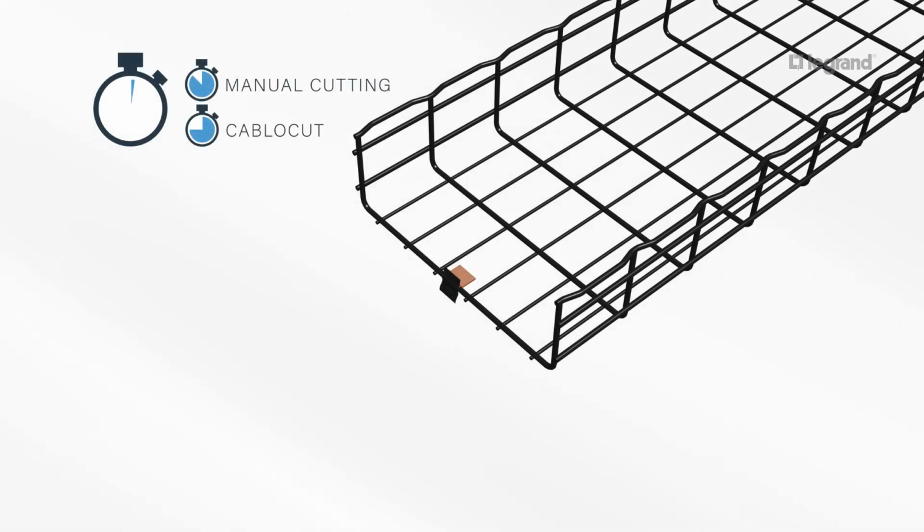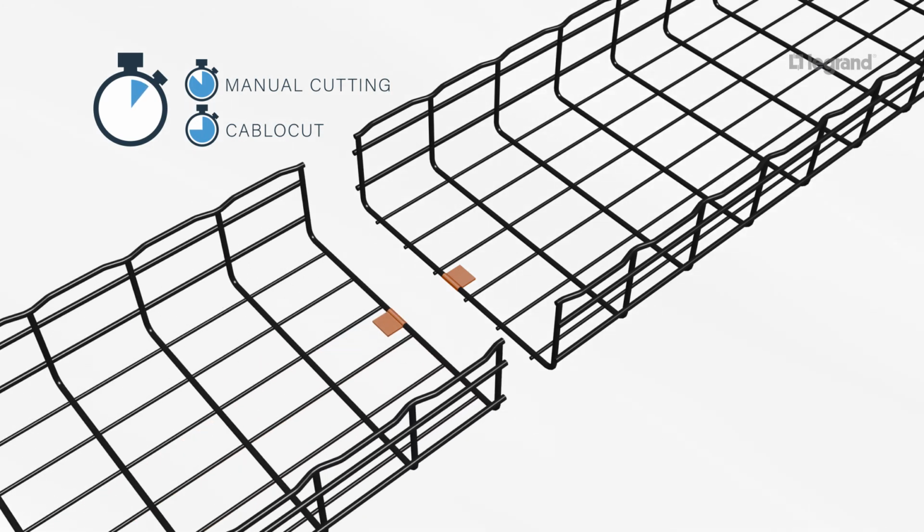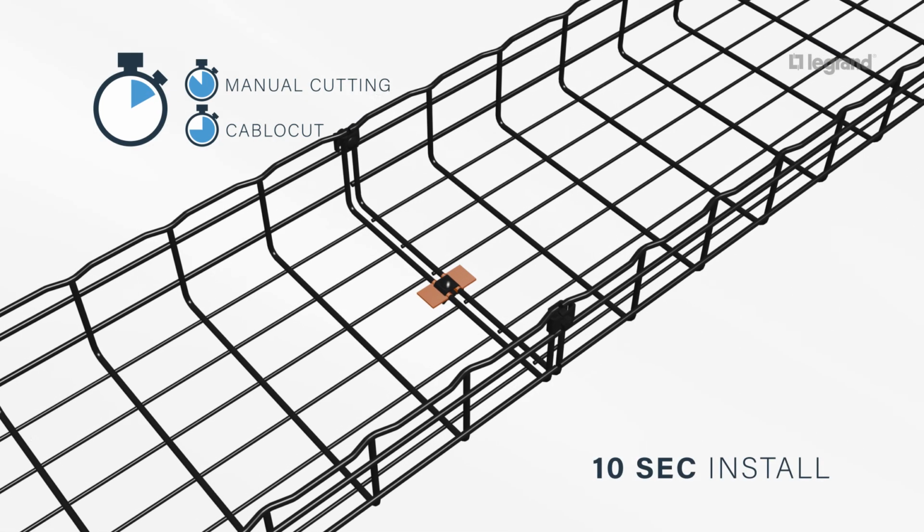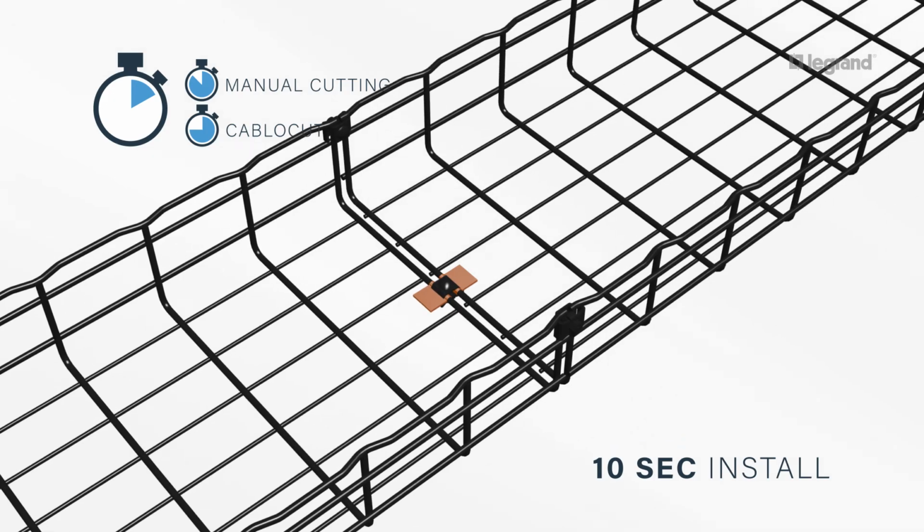Cablofil painted trays provide a UL-rated bonding location on the end of every tray. Use a utility knife or screwdriver to loosen the edge of the painted over masking tape covering the bonding strip. Position tray so that the exposed copper strips are aligned, and use SWKs to join tray sections. Add another SWK to the bottom section over the copper strips for proper grounding.